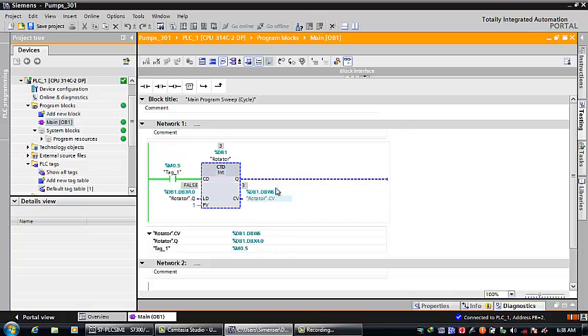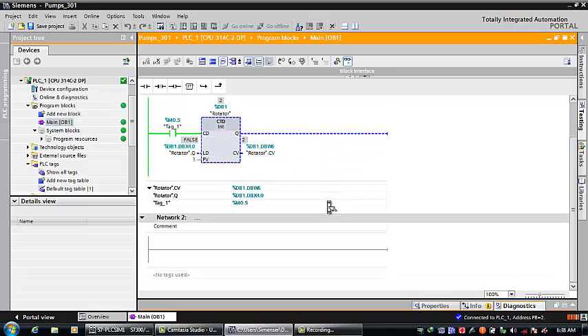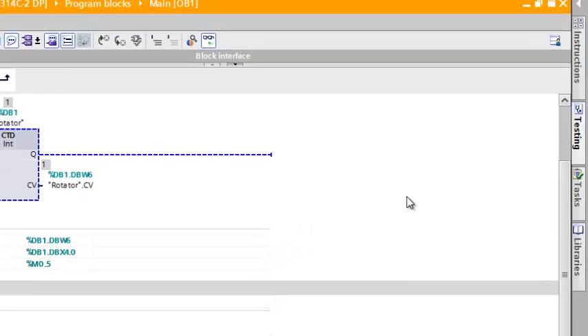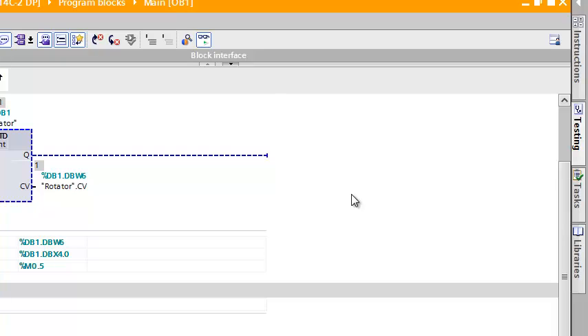Let's see what I got. Okay. Everything is okay. My counter is working. 3, 2, 1, 3, 2, 1. This is what I want. I want nothing else. Now, the value appearing here will be replaced as soon as we finish the project. So it will be replaced by an hour meter that counts the hour of every pump and shift the pumps according to the minimum hours. If pump number 1 has the minimum hours, the rotator is going to use number 1 and so on. Let me show you how the pumps are rotating according to this value.